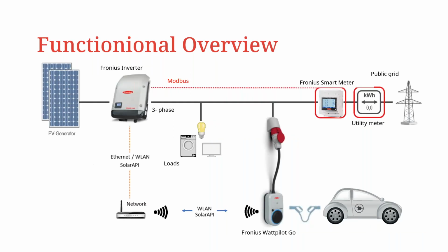So this is just a functional overview of how your system would interact with your Wattpilot Go. You'll have a normal system with your Fronius inverter and your original grid meter, as well as your normal loads that are covered by your Fronius inverter. Your Fronius Wattpilot Go is just an additional add-on feature, so it ties directly into the system itself. It doesn't need additional cable running from the inverter, for example. It can tie into an existing system.